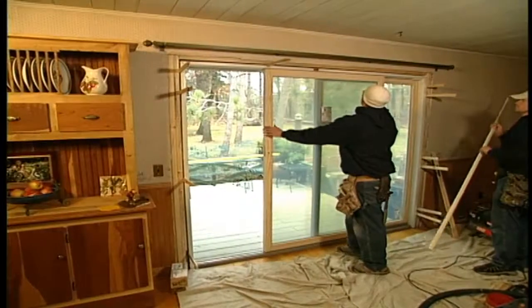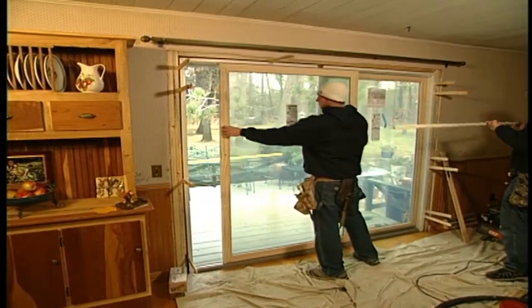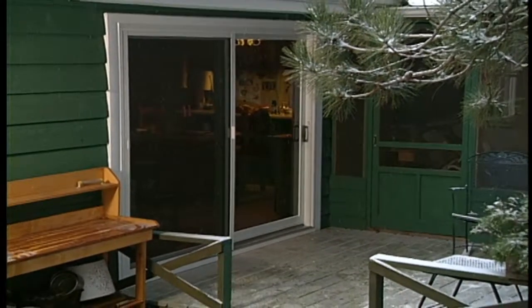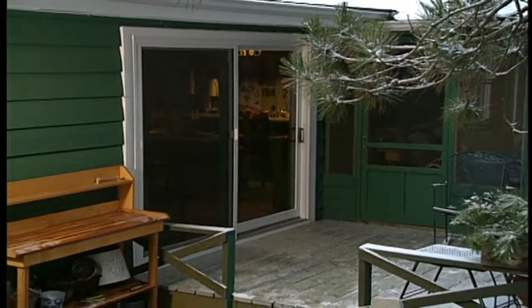Customized for them. The other important thing is if the homeowner's made any changes, in the case this is going to be a replacement, have they made any upgrades to the home that we would need to take into consideration for sizing requirements? What type of upgrades are you talking about that can affect an air conditioning performance? Well, if they would have upgraded windows, doors, re-insulated, all those types of things change the thermal performance of the home. We need to account for that when we're doing our load calculations and coming up with a proper size system for them.